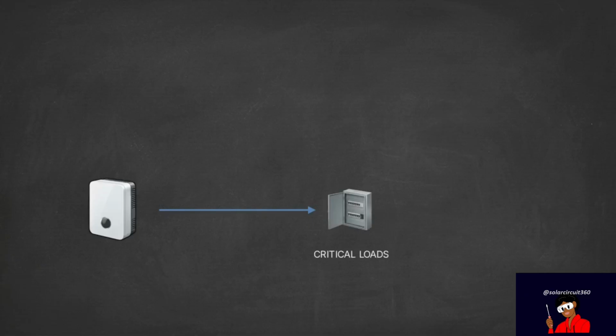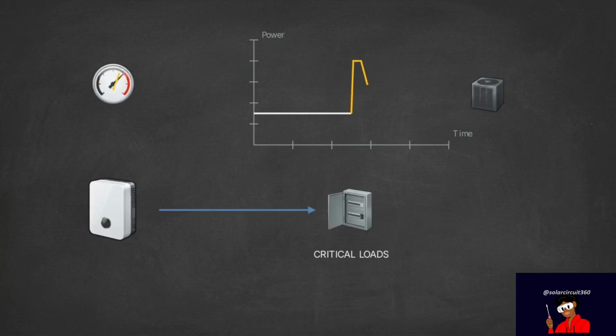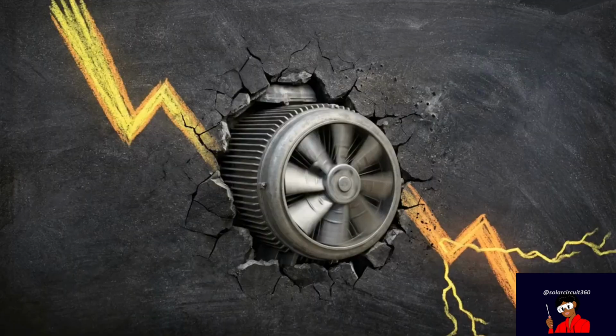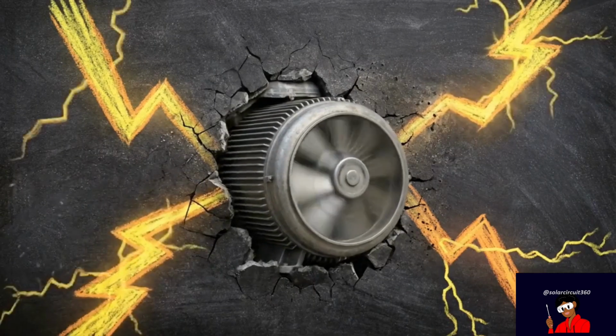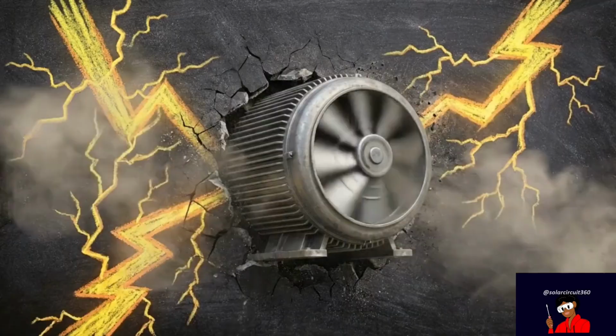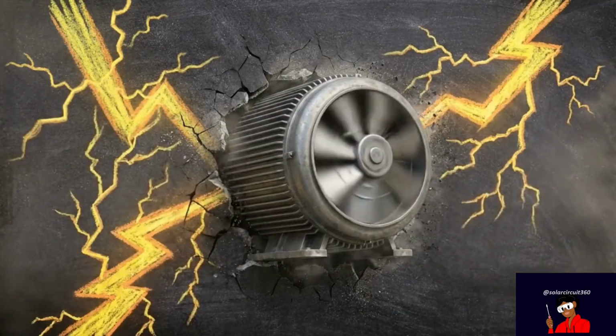On the output side, power routes from the inverter to the home's critical loads panel. Determining standard continuous demand requires summing the exact wattage of these essential loads. During backup operation, essential loads must be physically isolated from the main panel. While standard draw looks stable on a graph, the system faces a surge capacity bottleneck. Starting heavy motors requires a massive power spike, often double the continuous wattage. High-surge household appliances like well pumps and HVAC compressors demand this immediate influx of current to turn their internal coils.